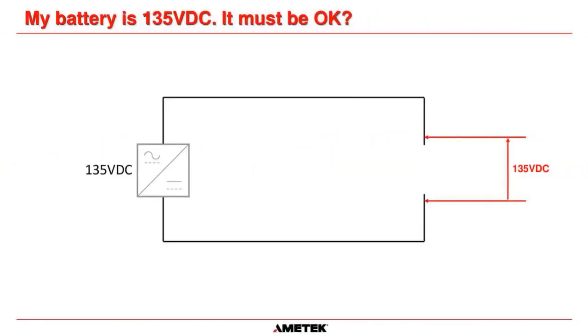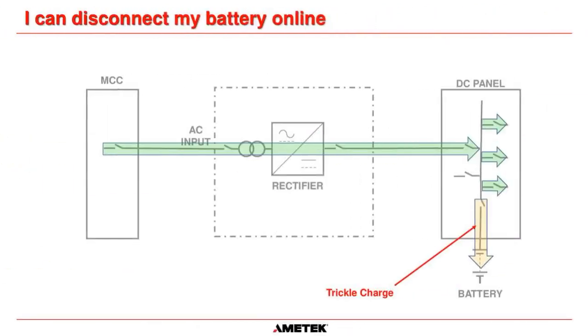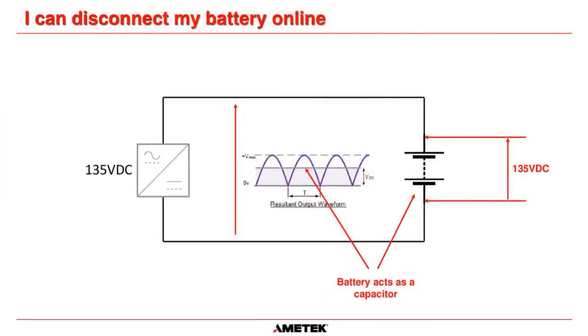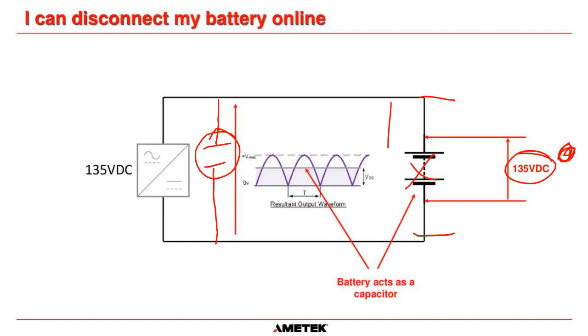Okay. What they do, the charger, for a filtered charger, they will have a bank of capacitors connected here. And for a battery eliminator, all they do is put a whole load more capacitors in there. So when you remove the battery, it does keep the voltage going out at 135 volts DC. But going back to Bill's question, if you have a fault out here and you need to clear it, the exact same thing is going to happen. The output voltage of this charger is going to drop down without a battery.